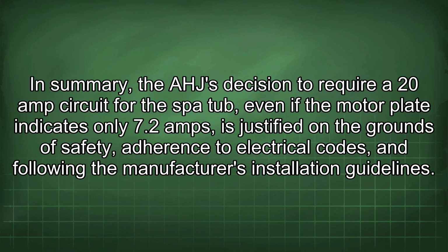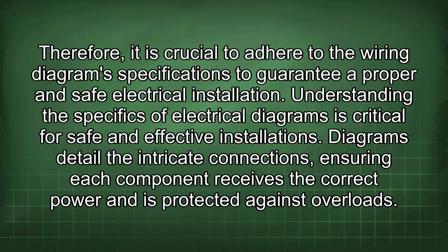In summary, the AHJ decision to require a 20 amp circuit for the spa tub, even if the motor plate indicates only 7.2 amps, is justified on the grounds of safety, adherence to electrical codes, and following the manufacturer's installation guidelines. Therefore, it is crucial to adhere to the wiring diagram specifications to guarantee a proper and safe electrical installation. Understanding the specifics of electrical diagrams is critical for safe and effective installations.